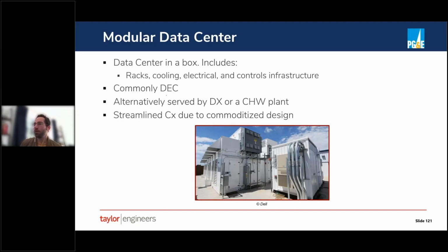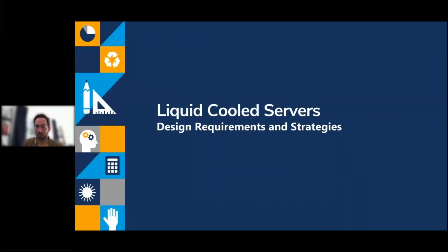These systems are commonly direct evaporatively cooled, but you can also get them with DX systems or served by a chilled water plant. From an owner's perspective, one of the nice things about these systems is that they are commoditized. They can streamline the commissioning process. There is an example of data centers that Jeff and I worked on, maybe back in 2016 and 17 at this point, where we commissioned 6 or 7 of these per site. Certainly the first 1 or 2, we found a number of issues, but after the first couple, the amount of rework or commissioning time was reduced substantially, because we're dealing with a commodity that's just repeated over and over again.